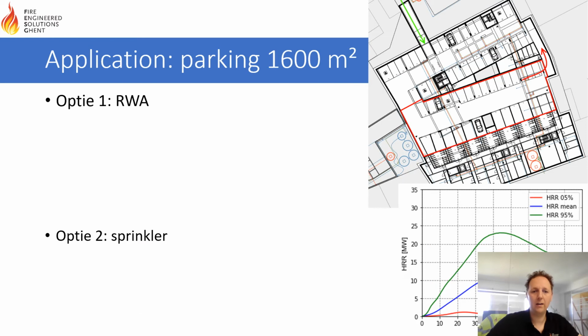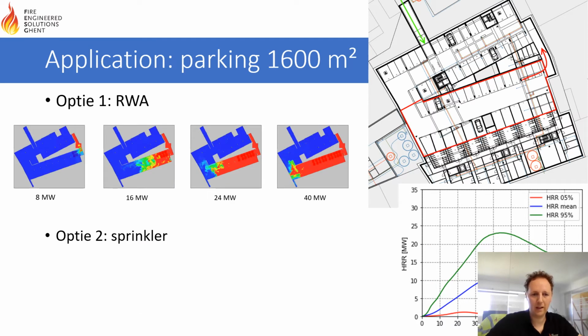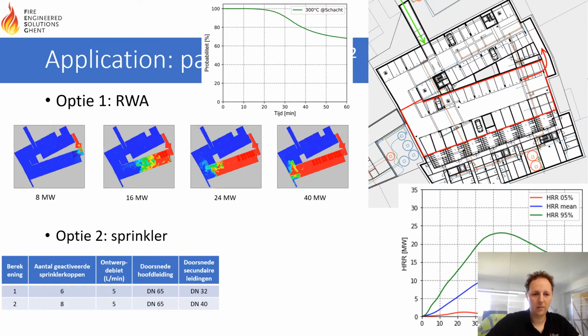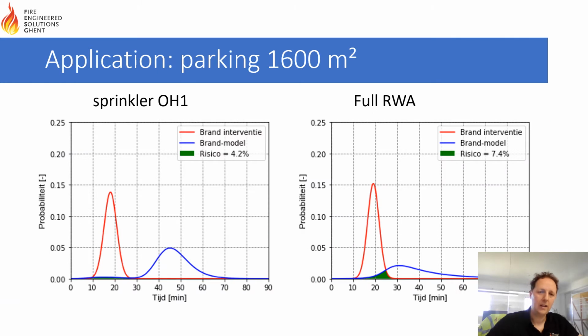Now, in order to apply it to a real case study, not going to go in detail, but basically you look at a car park where either you put a smoke heat control or you put a sprinkler system based on 6 heads, so OH1 instead of OH2, and you compare the safety level. Then you have the first distribution, that is the distribution for fire brigade intervention. The red curve will not change in both options, but the distribution for fire spread will be significantly different in case of a sprinkler system compared to a smoke heat control, and that will result in a residual risk that you can compare between the sprinkler and the smoke heat control system.